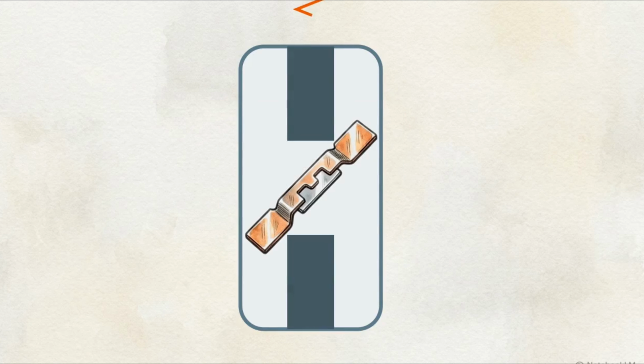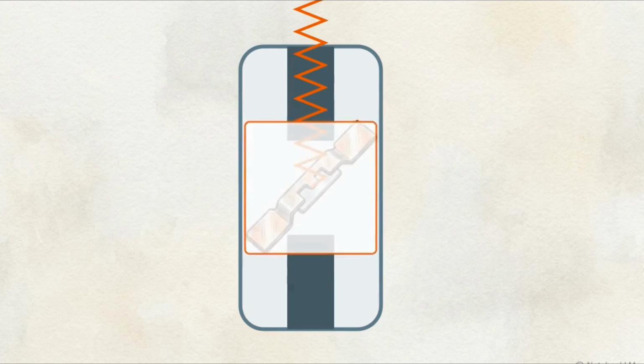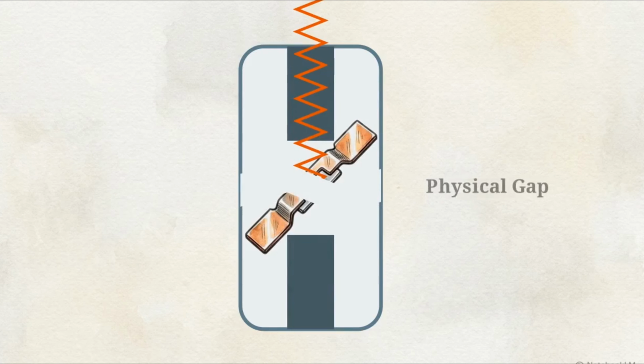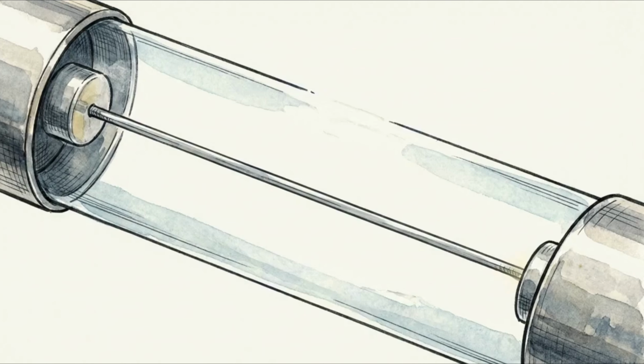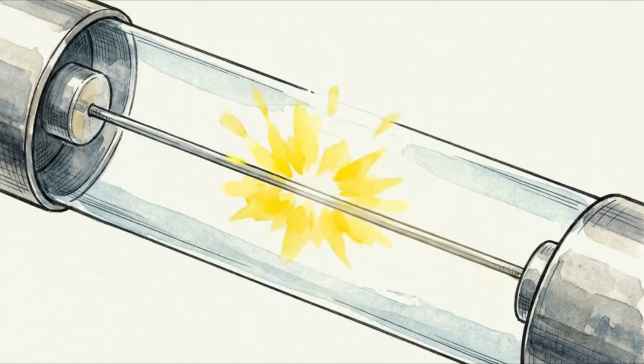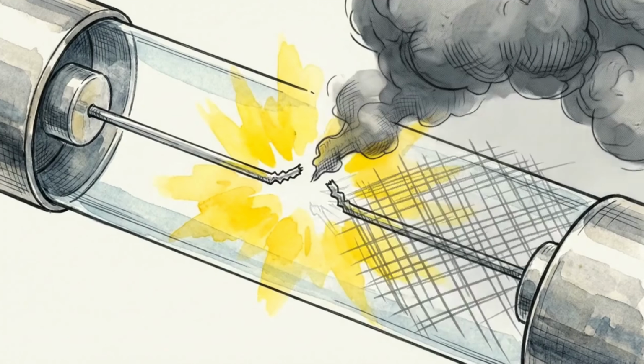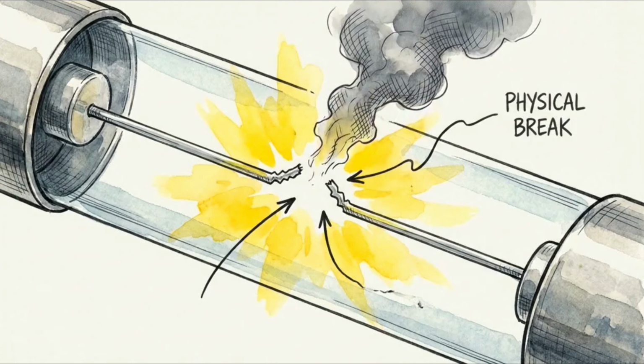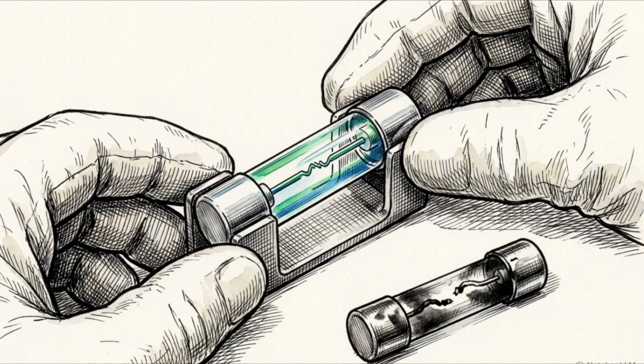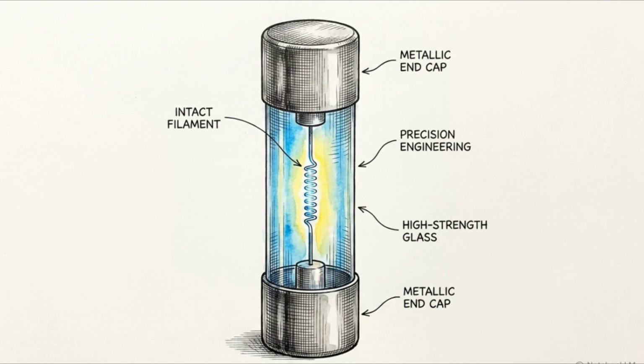This is a sacrificial element. When hit by an extreme, instantaneous spike of current, that internal wire overheats and burns through in milliseconds. By vaporizing its own internal wire, the fuse creates an absolute physical break in the circuit, ensuring the surge never reaches the downstream equipment. As this acts as a permanent physical destruction, the system remains offline until an operator clears the short circuit and manually replaces the dead fuses. Fuses provide a high-speed hard stop at the border of the circuit, destroying themselves to block catastrophic surges.